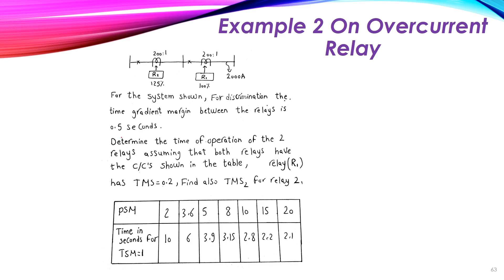Let's have another example. In the system shown, we have two protection relays R1 and R2. R1 has a pickup setting of 100%, which means it will operate at one times the CT secondary. R2 operates at 1.25 times the CT secondary. The CT used is 200-to-1, converting 200 amperes in the feeder to 1 ampere. The fault current here is 2000 amperes.